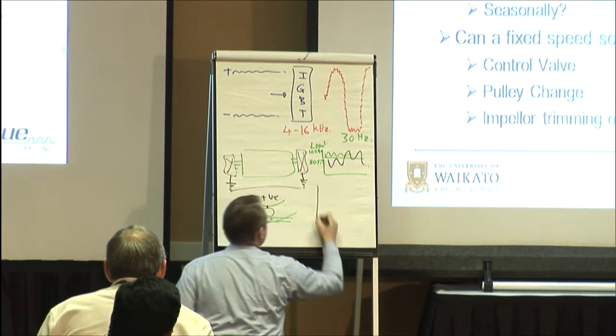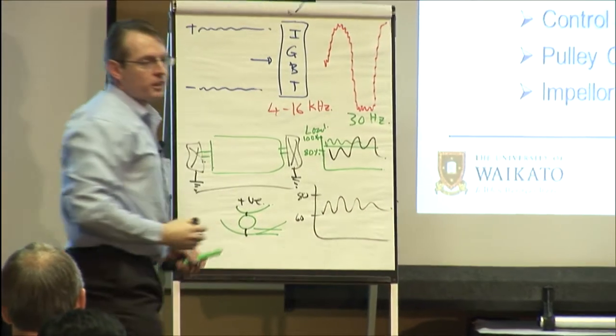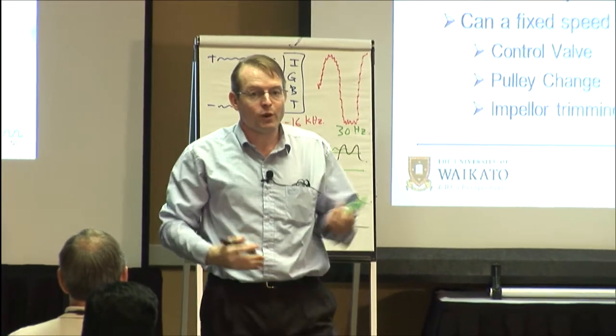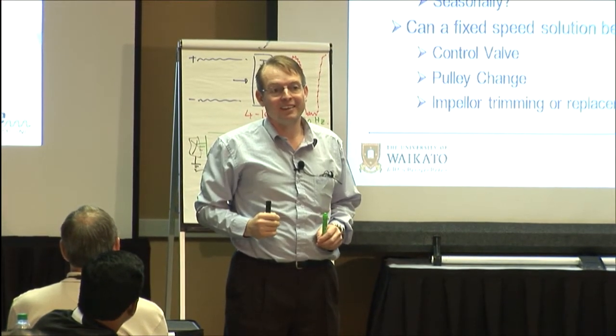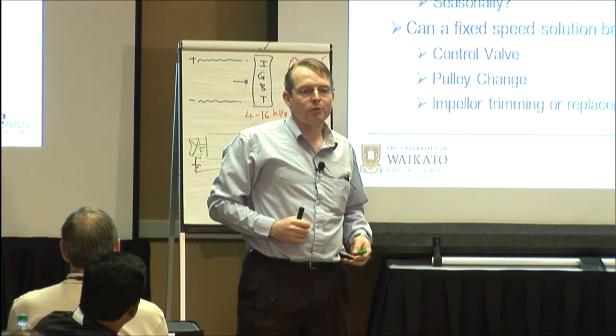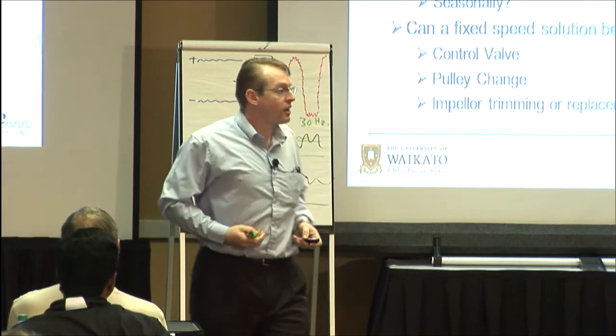If your demand is like that, what do you think? Resize it, right? If you've got 15, 20% variation max, you don't need a VSD. Okay? It's a matter of sizing. Why do a lot of people throw a VSD on a system, and a cheap one at that? It's because the design engineer doesn't know how big to make it.